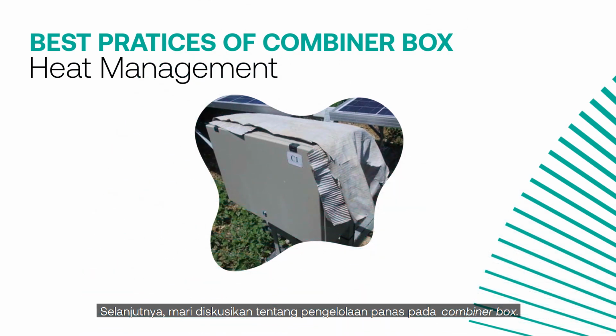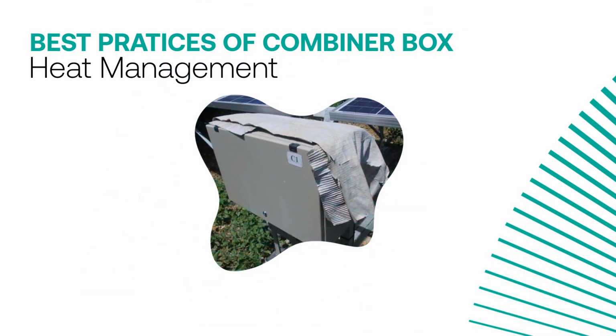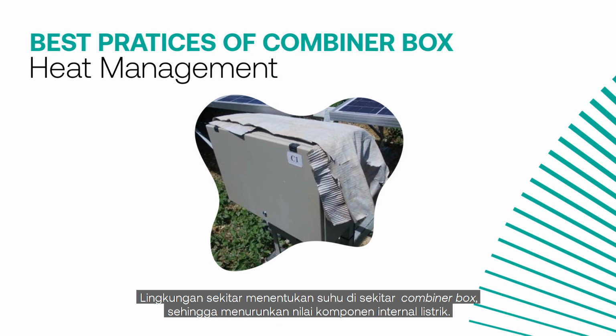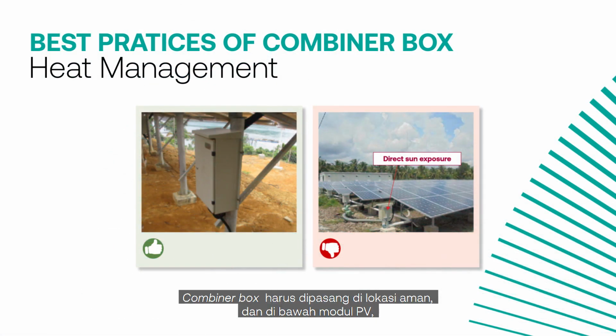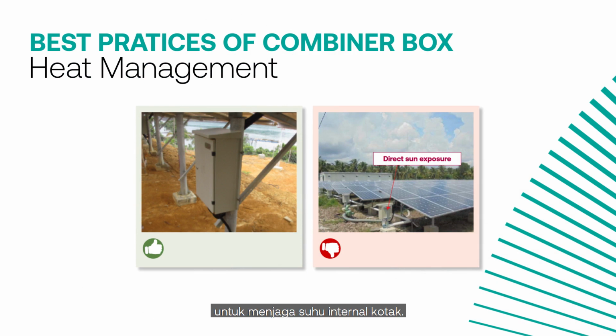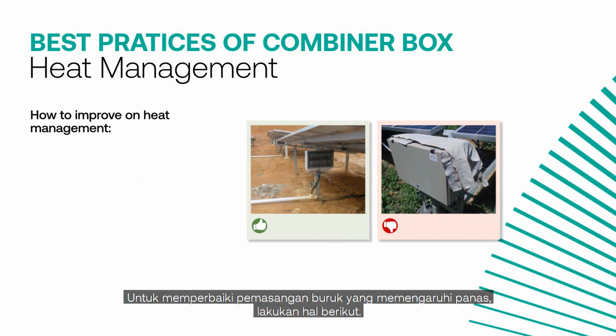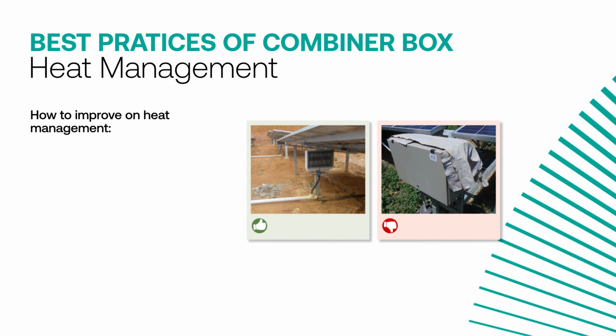Next, let us discuss heat management of the combiner box. The surrounding environment determines the ambient temperature of the combiner box, and thus derates the internal electrical components. The combiner box must be installed in a safe location and below the PV modules to maintain the desired internal temperature of the box. To improve a bad installation that affects heat management, do the following.